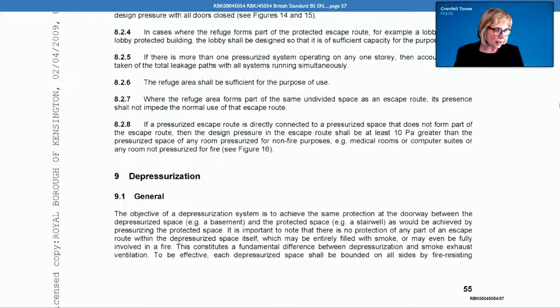There's a section on depressurization within this standard. It says the objective of a depressurization system is to achieve the same protection at the doorway between the depressurized space, e.g. a basement, and the protected space, e.g. a stairwell, as would be achieved by pressurizing the protected space. It goes on to say it is important to note that there is no protection of any part of an escape route within the depressurized space itself, which may be entirely filled with smoke or may even be fully involved in a fire. This constitutes a fundamental difference between depressurization and smoke exhaust ventilation. Do you see that? Yep.